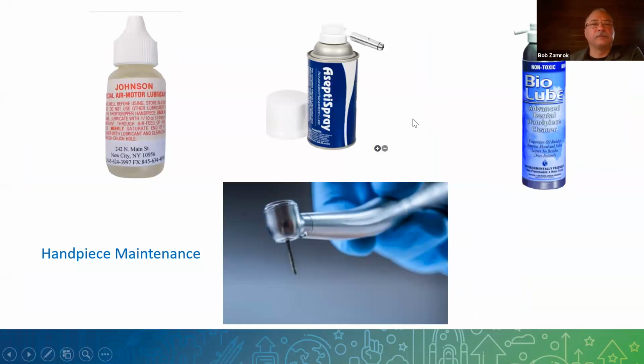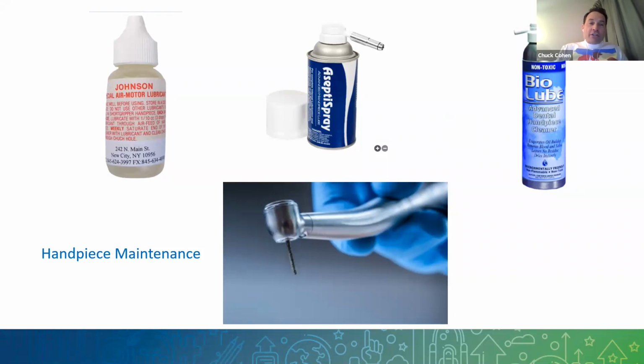Hand pieces—let's stop for one second. The one thing I wanted to add is that the autoclave is absolutely one piece of equipment where you should have extra parts in your office ready to go. If you need a gasket or whatever, ask your trusted service professional for your specific autoclave to get the right gasket, the right filters. You can fix a lot of things yourself if you have the right parts. It's always a good idea to have spares, because the service tech who shows up may not have the right part, and then you're out for another day. So ask your service professional what parts you should have in your office to do routine maintenance on your sterilizer in an emergency. You agree, Bob?